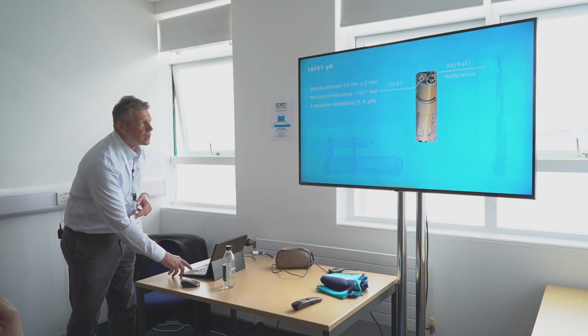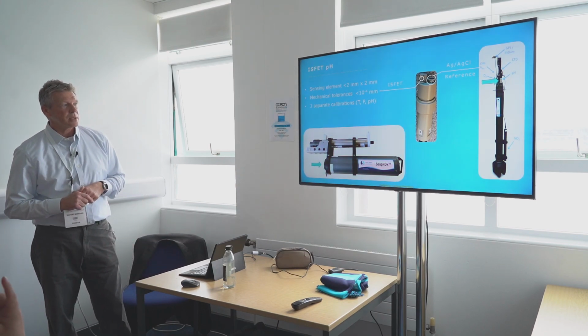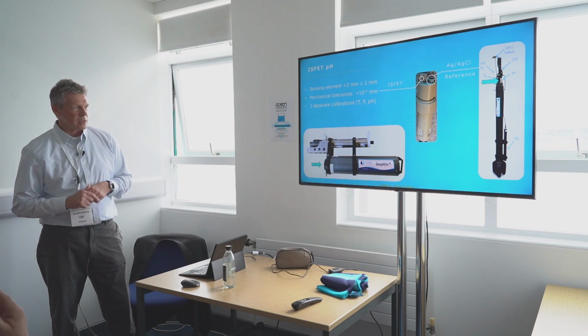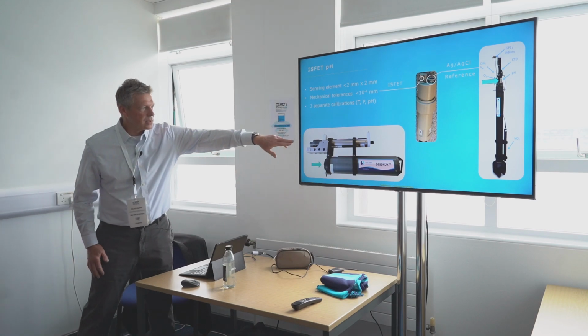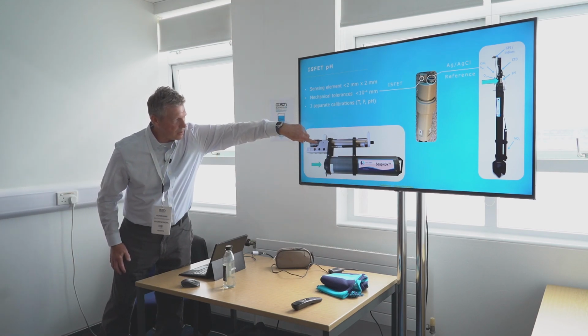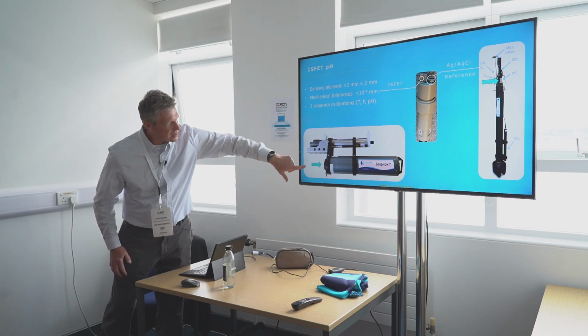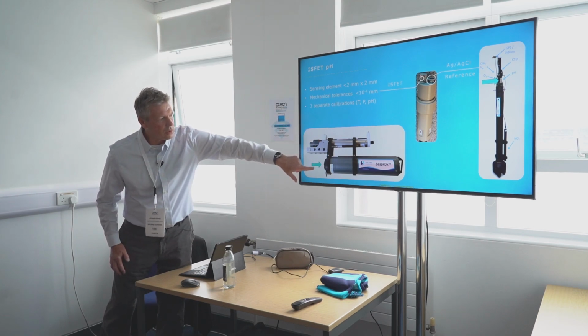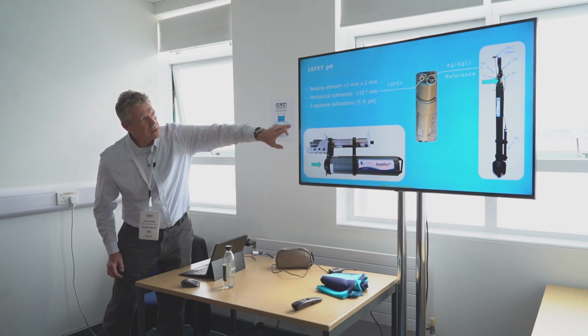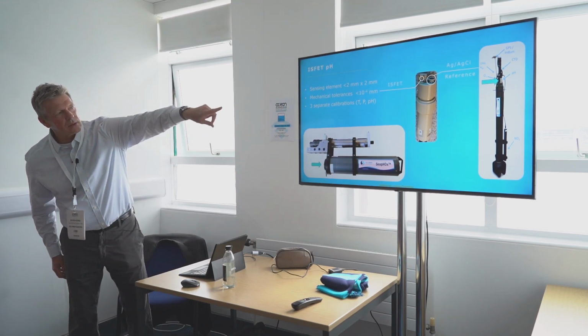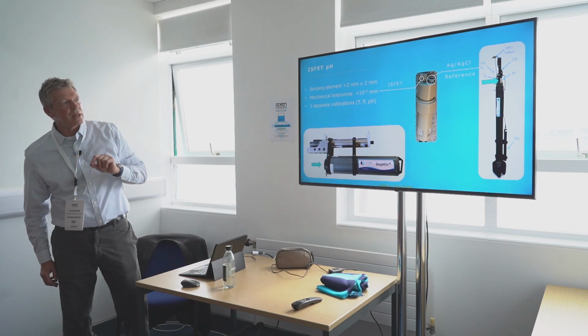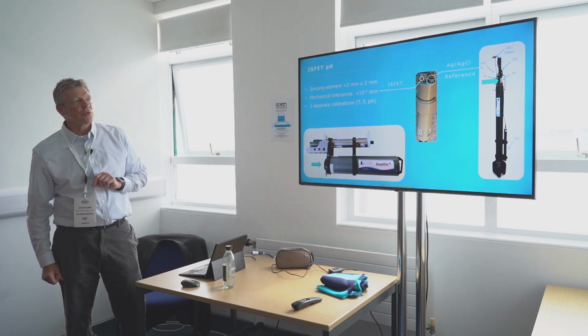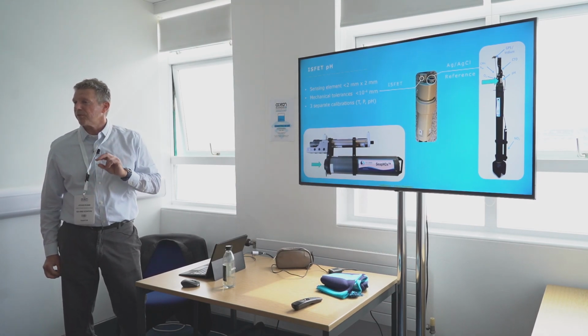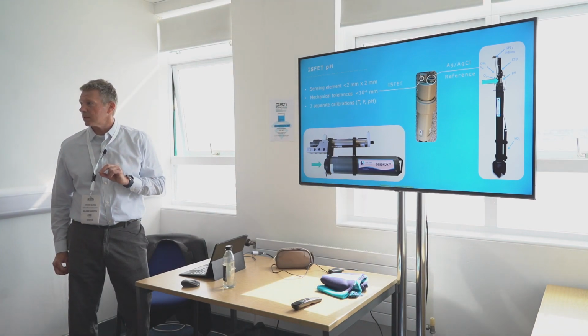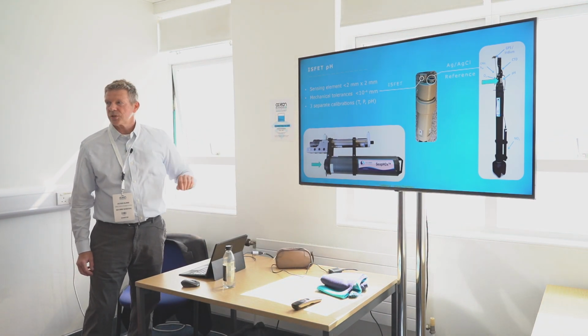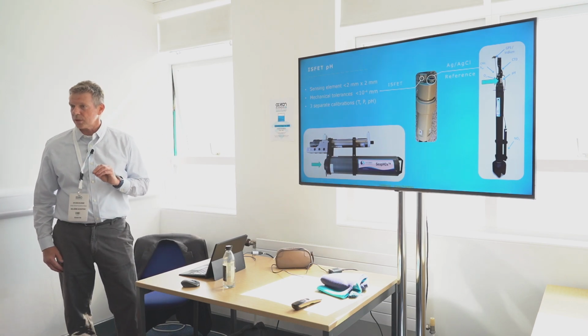So we have this technology implemented in 2 different types of instruments. We have the Seafox, that's basically, you can see here, combined with a microhead. The sensing element is shown by the green arrow. And it's also integrated on a Navis float. You can see it on the very right side. It says pH there where the green arrow is. That's a profiling instrument, but it's typically profiling very slowly, about 10 centimeters per second. And on the Seafox application, it's really used in a moored mode.